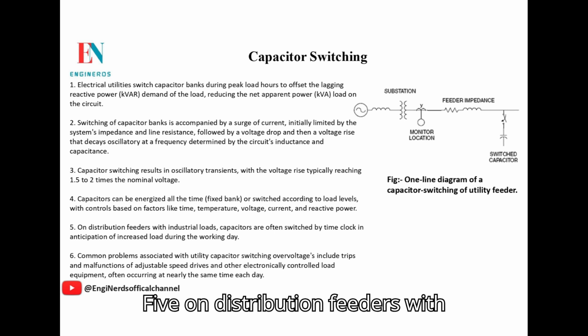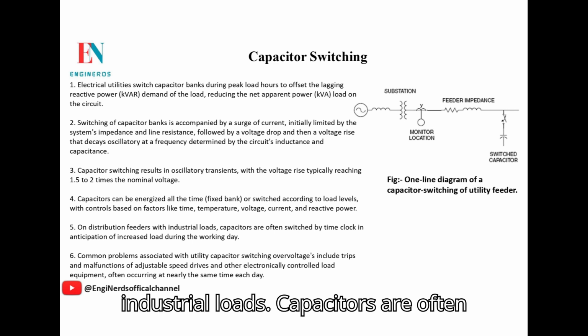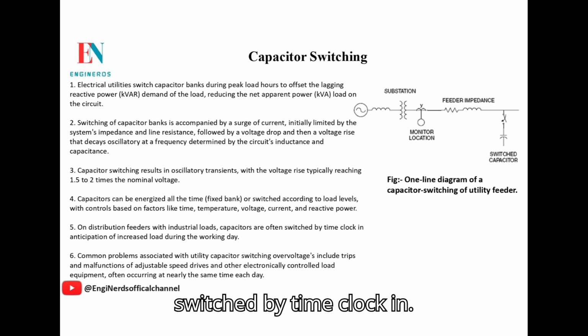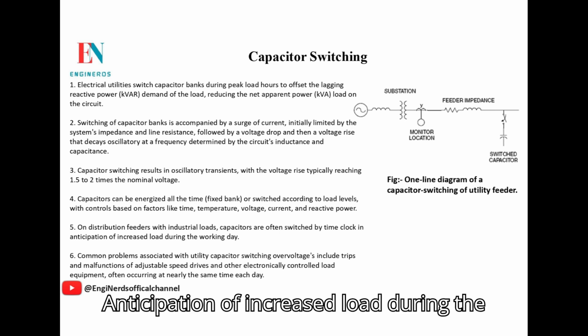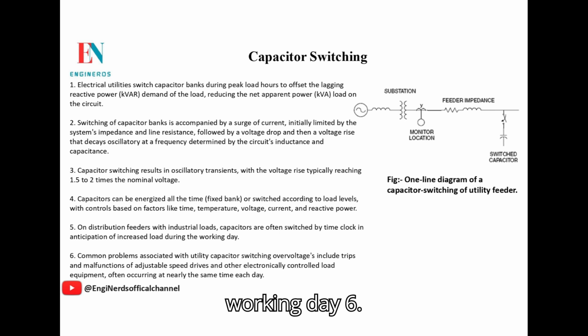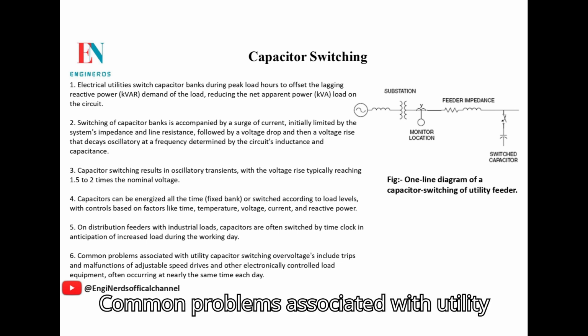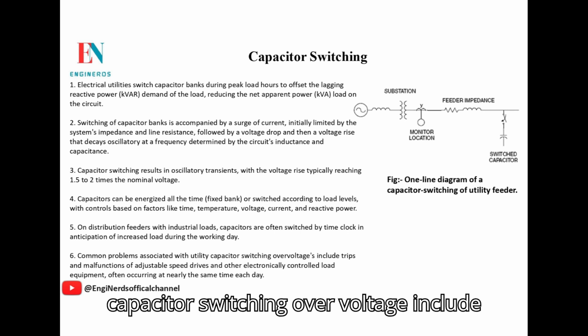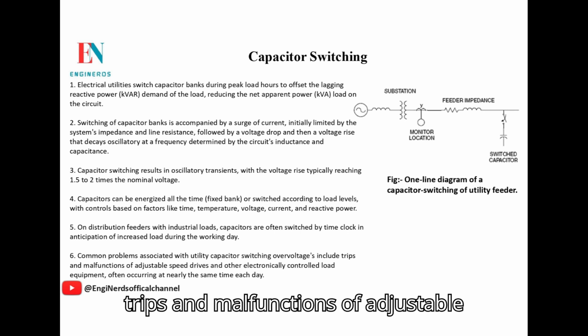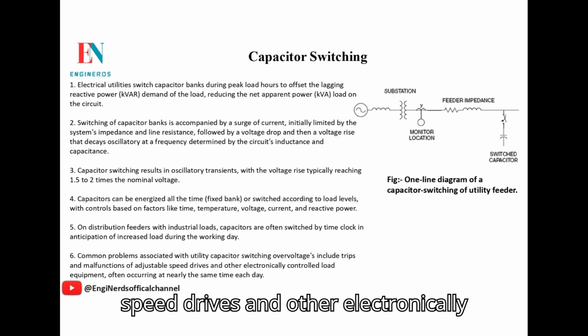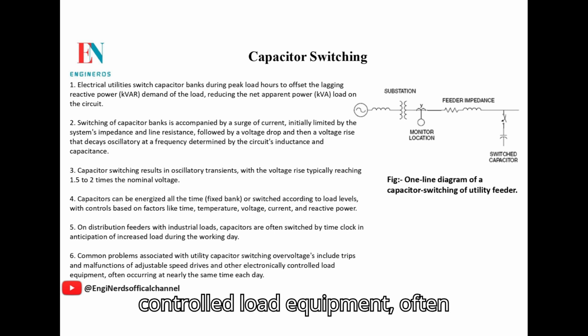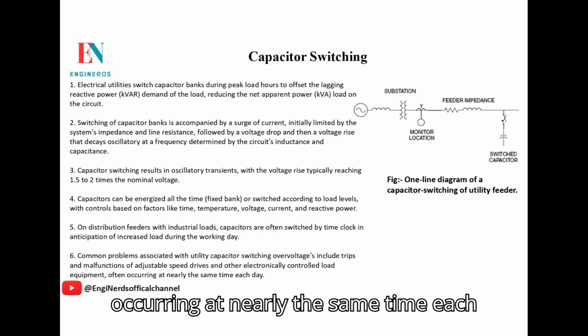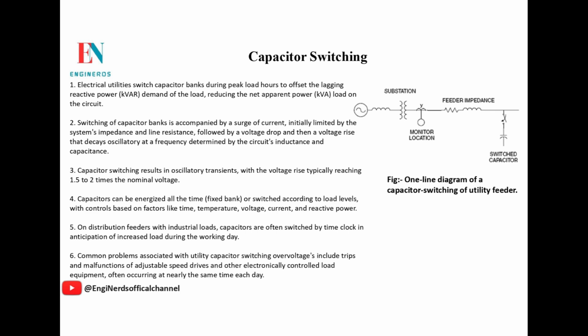5. On distribution feeders with industrial loads, capacitors are often switched by time clock in anticipation of increased load during the working day. 6. Common problems associated with utility capacitor switching overvoltages include trips and malfunctions of adjustable speed drives and other electronically controlled load equipment, often occurring at nearly the same time each day.